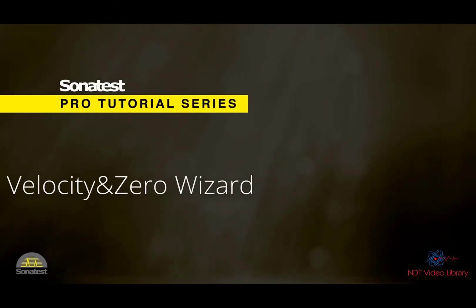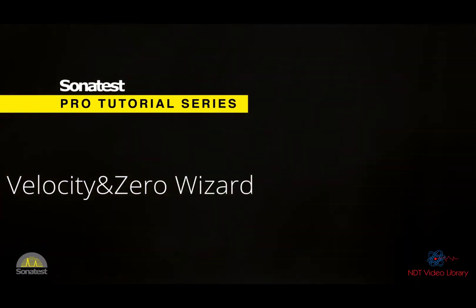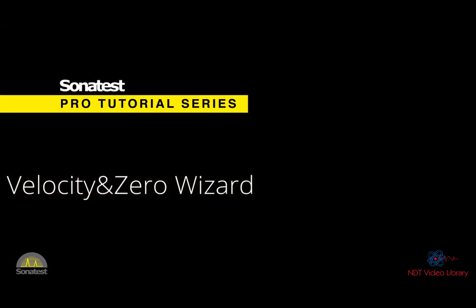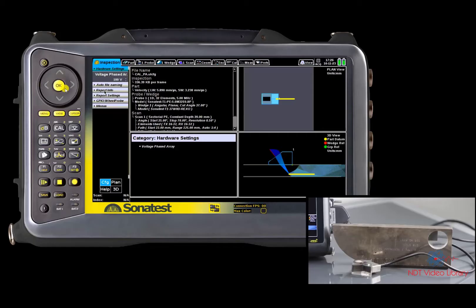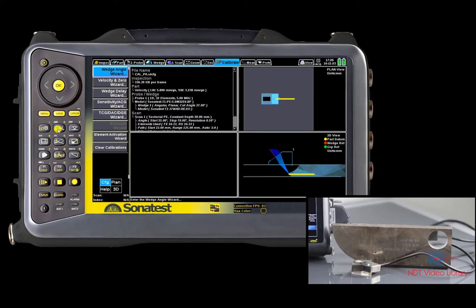Hello everybody. Today's tutorial is about velocity and zero calibration. This calibration sets the speed of sound value of the calibration block material and the appropriate delay zero for the beam used in the calibration. For this calibration you're going to need a Veo+ or Prisma instrument, a phased array probe, and a reference block. We are using the same setup as in the previous video and are going directly into the velocity and zero wizard.